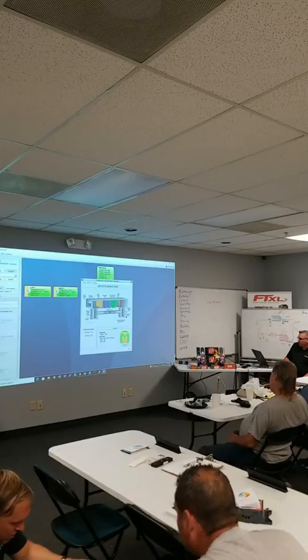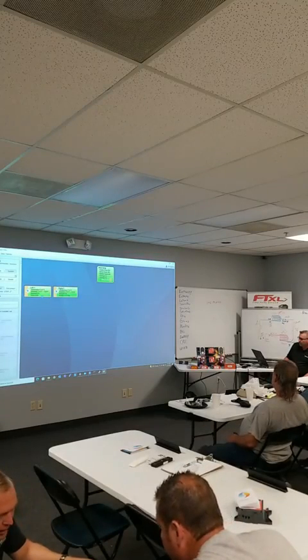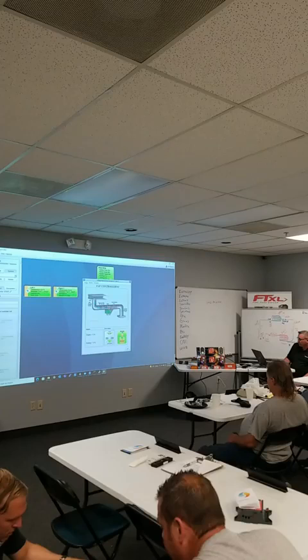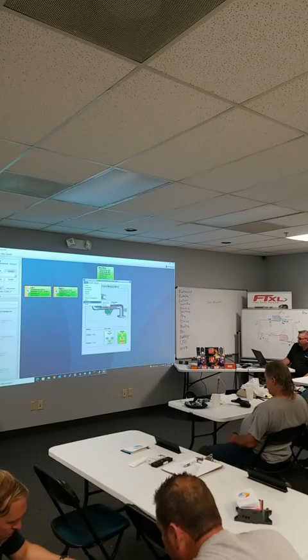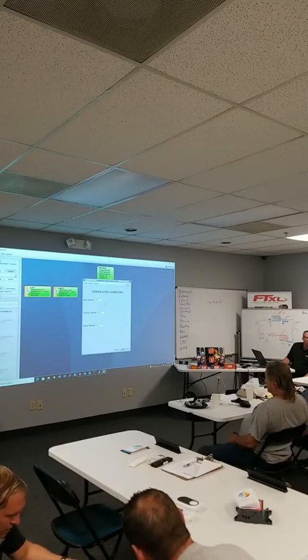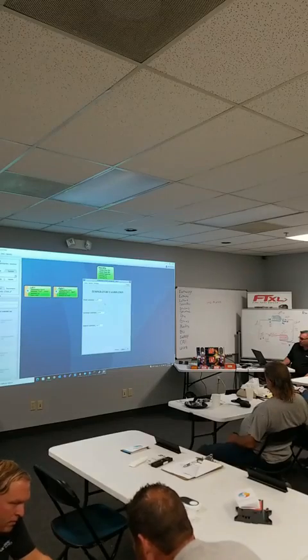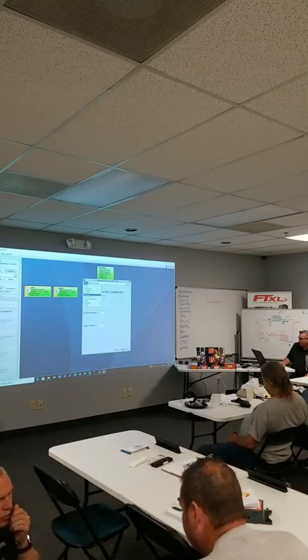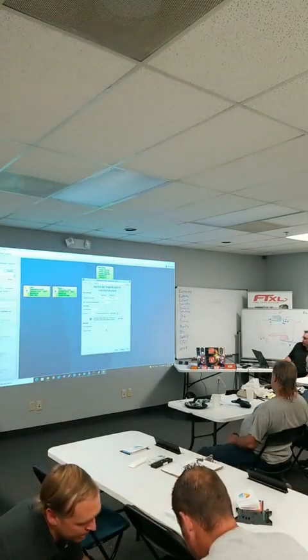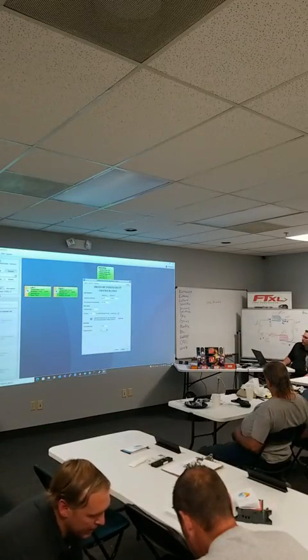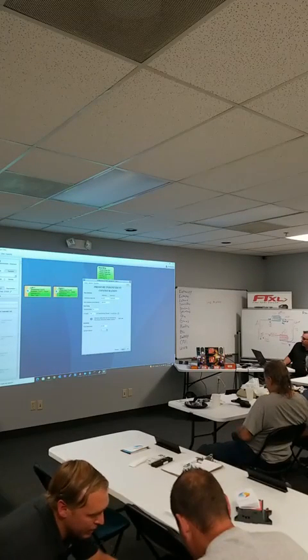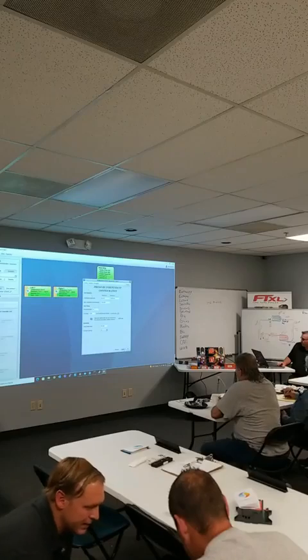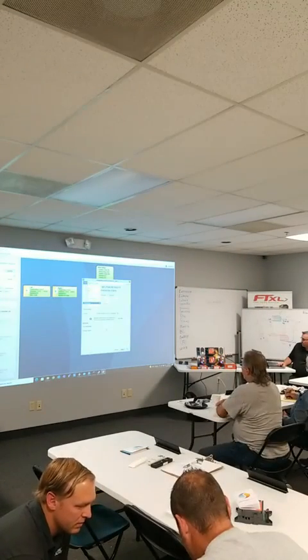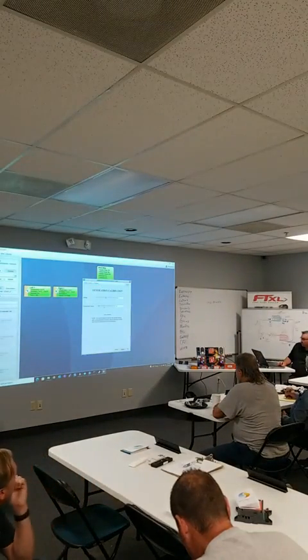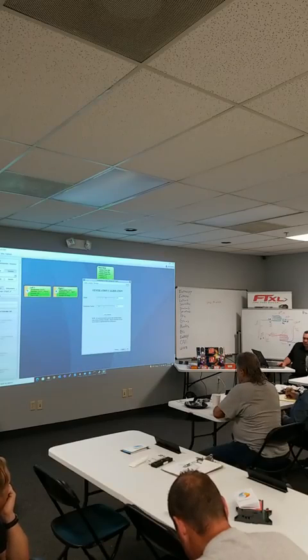So the VAV controller, everything is exactly the same with the exception of, oh, there was something I did miss. If you need to calibrate the room temperatures or discharge for the set point, you can. The big difference in the VAV is you need to put in what the CFM set points are, the box size, the K factor. If you don't know, we actually have an auto calibrate process that you can do with the balancer. Hit it, it's going to drive open, and they're going to read all the diffusers.